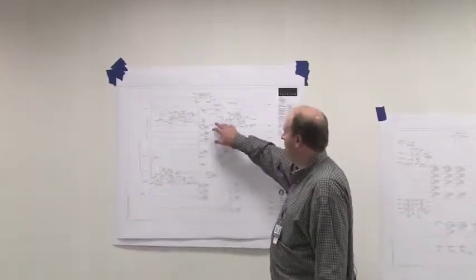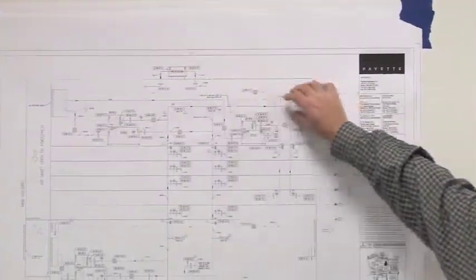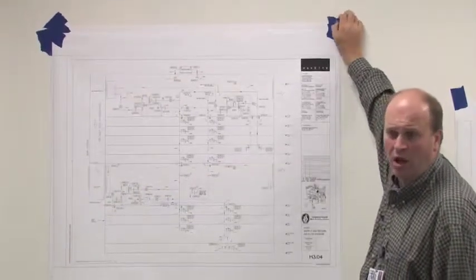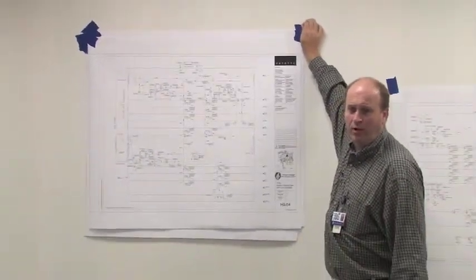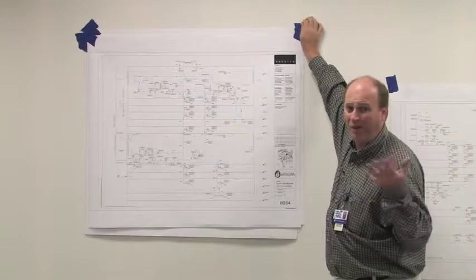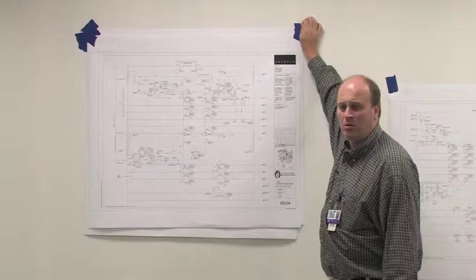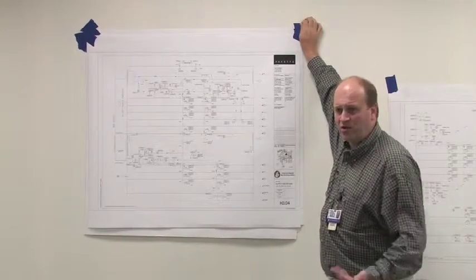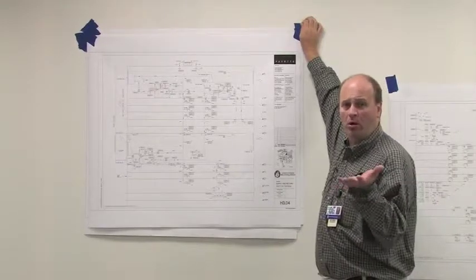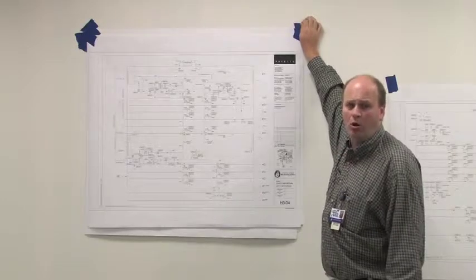There is also a unit on the roof ventilating the penthouse mechanical room and providing cooling up there, including air conditioning. This was done primarily for dew point control — mechanical rooms without dew point control see sweating on pipes, especially chilled water lines, bleeding through insulation and hangers. This building is one floor taller than all surroundings, so the mechanical room is essentially an island in the sky exposed to sun all day.